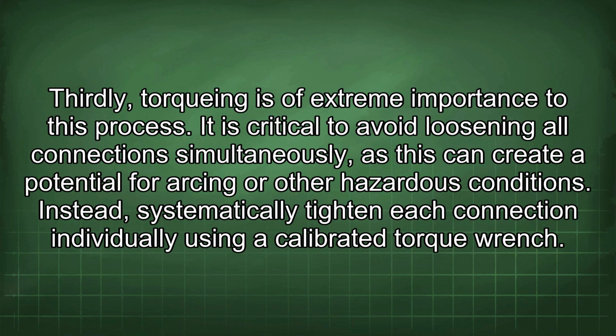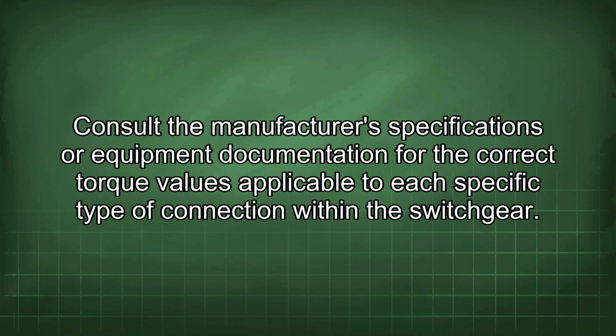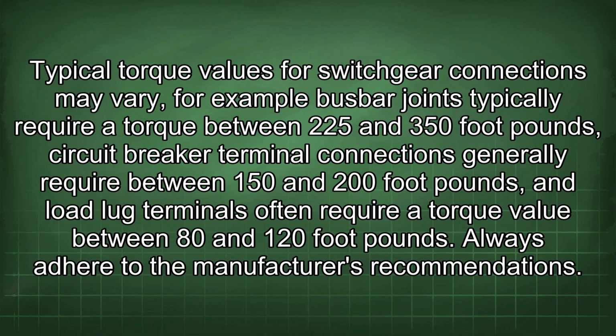Thirdly, torquing is of extreme importance to this process. It is critical to avoid loosening all connections simultaneously, as this can create a potential for arcing or other hazardous conditions. Instead, systematically tighten each connection individually using a calibrated torque wrench. Consult the manufacturer's specifications or equipment documentation for the correct torque values applicable to each specific type of connection within the switchgear. Typical torque values for switchgear connections may vary.